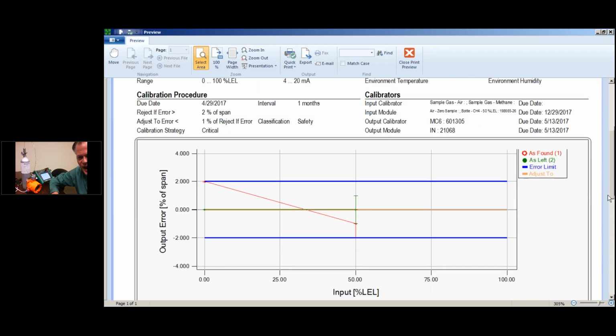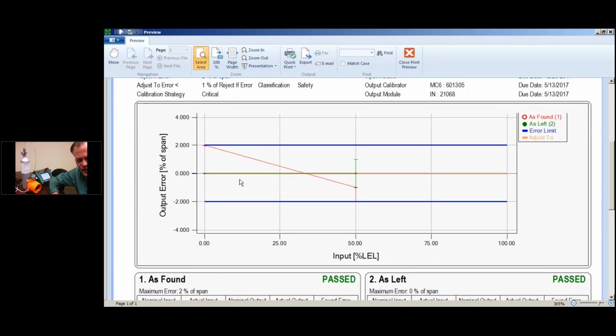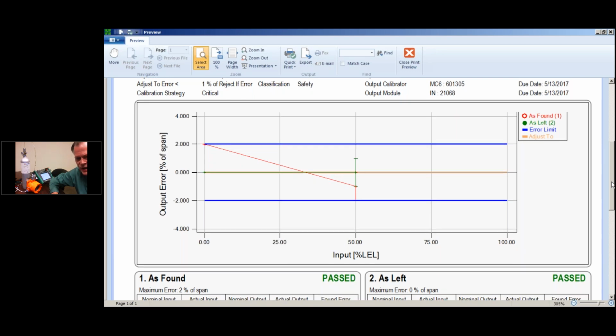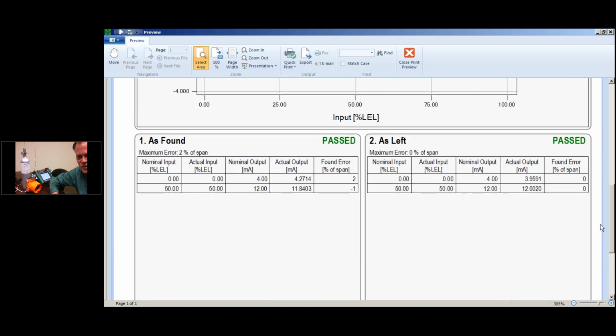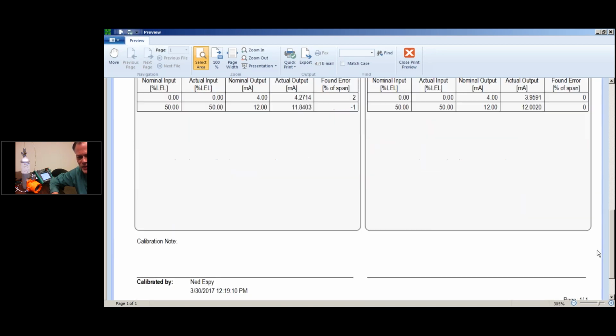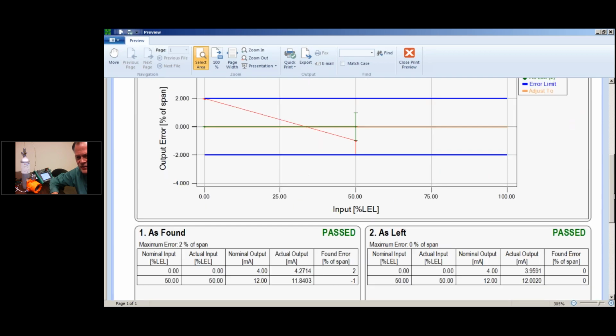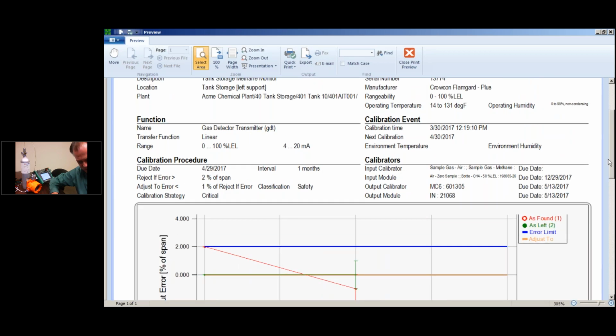And there's the graph as found, and then here's the as left, sort of this perfect line here. And then if we go down here, there's the numbers that were recorded by the calibrator. So fully documented test on a sample using sample bottles as our calibrator rather than a traditional electrical calibrator. So I'm going to turn it over to Katie.